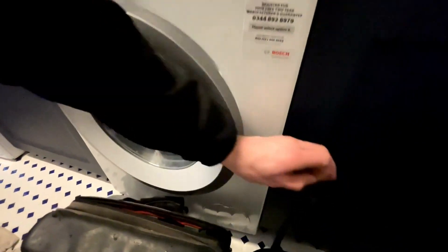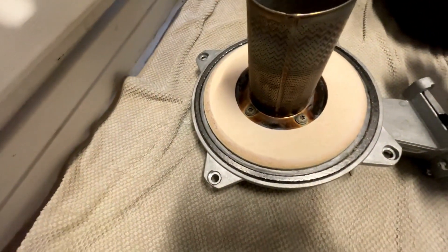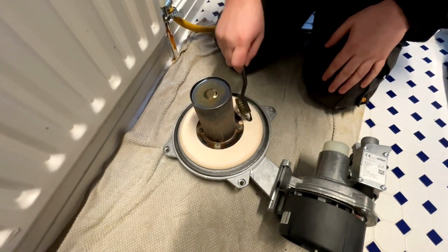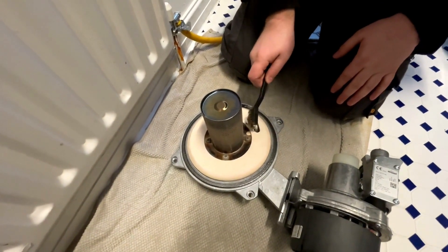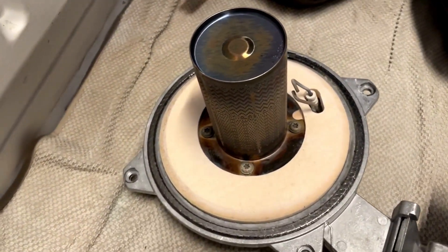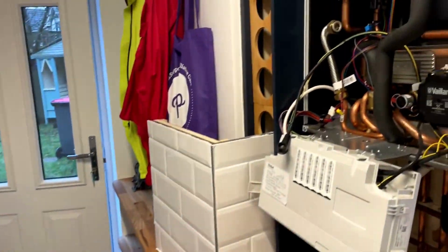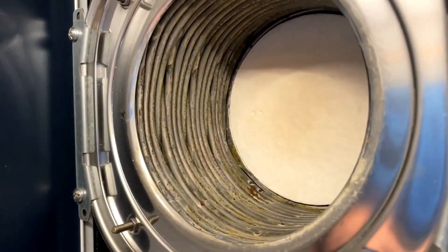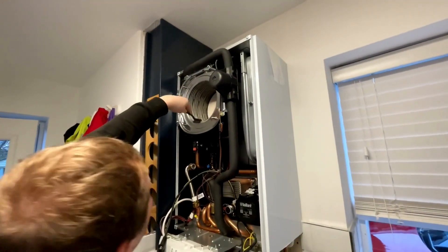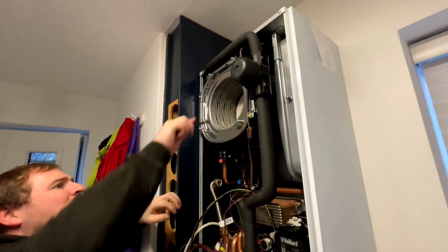Just see how good they are. When you're taking these apart, you need to be really careful with this seal, right? You need to be really careful with that seal, but you also need to give those a clean up. So what we have here — we've got a spark electrode, as you can see. Let's give them a clean up. Let's get them out and open it up. How are we looking? It's a bit dirty, isn't it? It's a bit dirty.